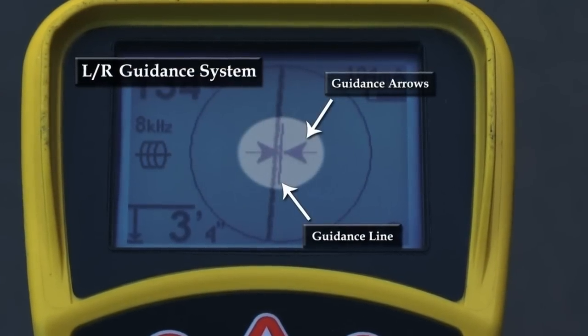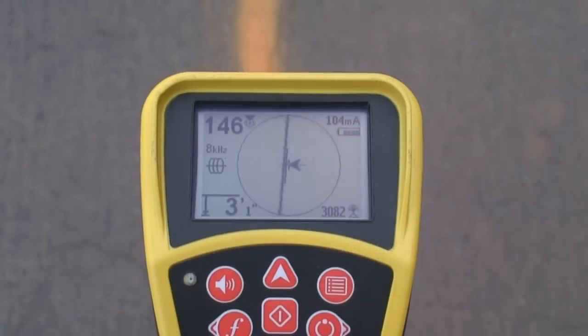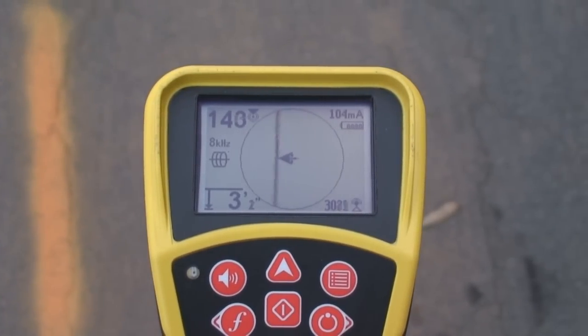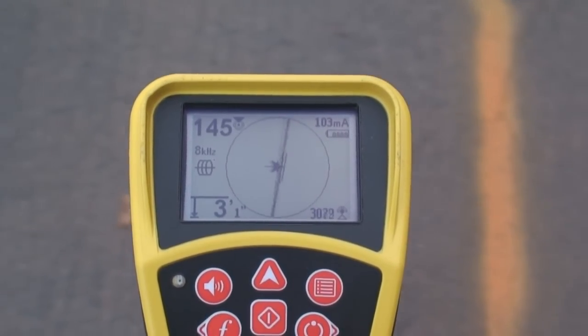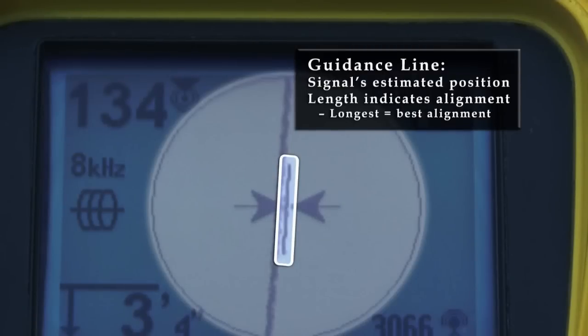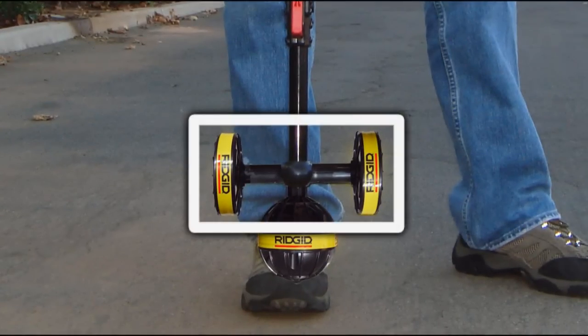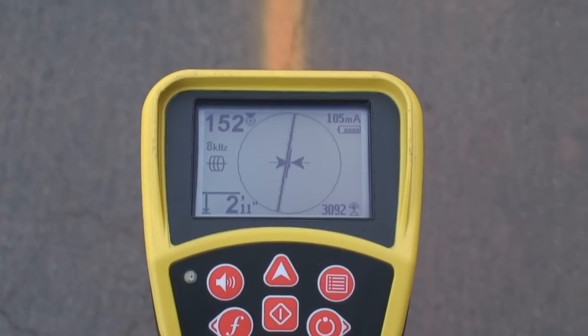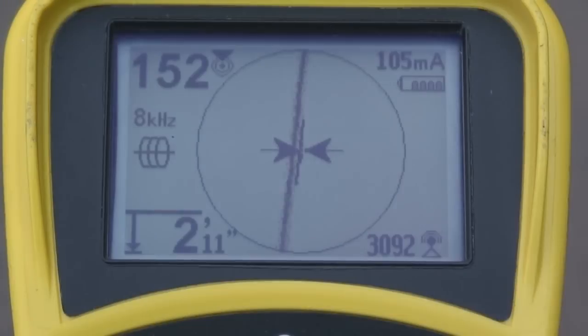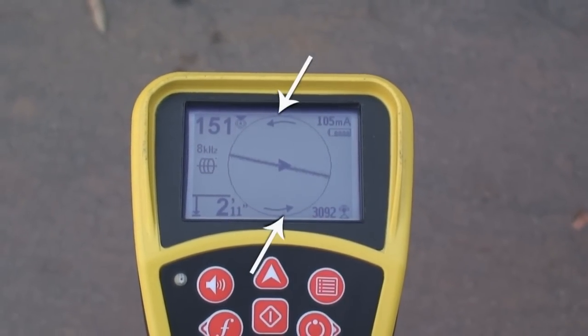Next we'll look at the left-right guidance system. This display element is independent from the tracing line and has two parts: the guidance arrows and the guidance line. When you move the receiver across the signal, the guidance arrows track the signal in real time, pointing in its estimated direction. When you're directly over the signal, the arrows will point inward to the center of the display. The guidance line serves two functions: it's a visual aid that helps you see where the guidance arrows place the signal's estimated position, and it helps you align the receiver with the signal. Unlike the tracing line, the guidance arrows are measured with highly directional antennas that are most accurate when aligned with the signal. The guidance line changes length to indicate your alignment — it will be longest when your alignment is best and will shrink as you become less aligned. When you're too far out of alignment, rotation arrows will appear to help you get the receiver back in alignment.